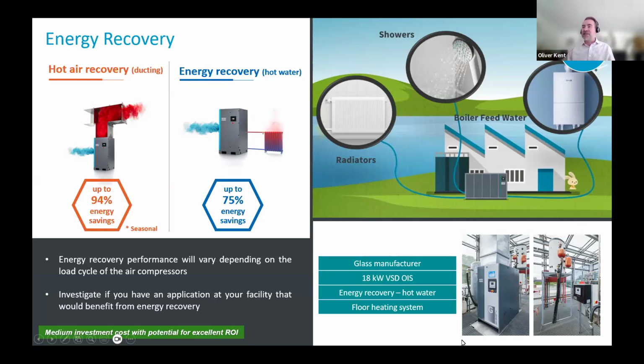We've got an example here of an energy recovery system fitted. In this case, it was a glass manufacturer. They only had a small compressor, an 18 kilowatt compressor, and yet energy recovery was giving them some really good payback, especially in this era of high energy costs. They were using the energy recovery in a floor heating system.